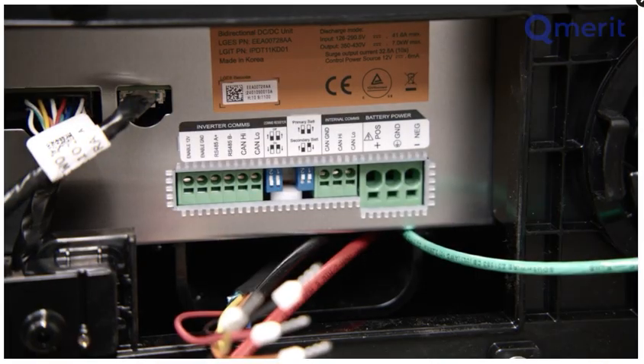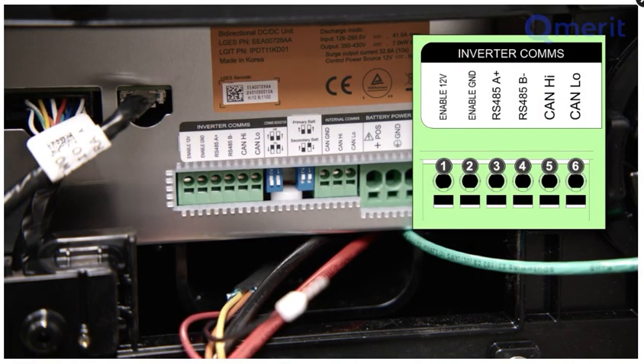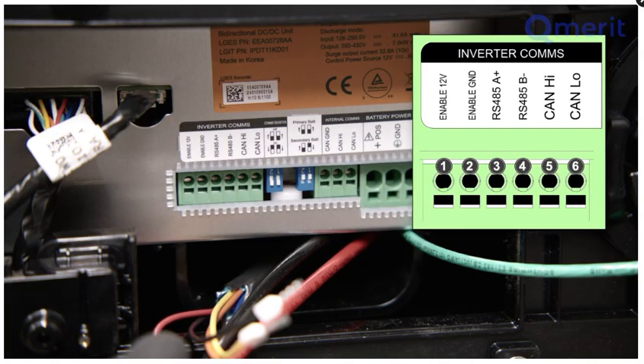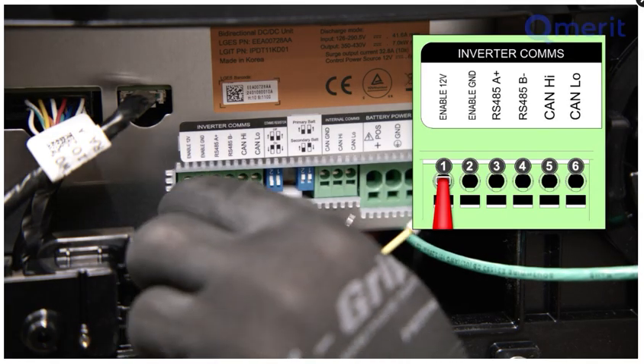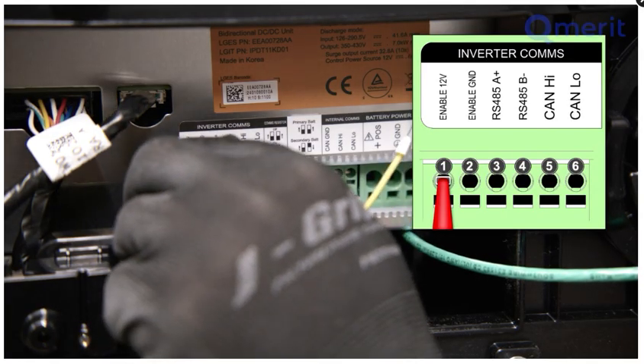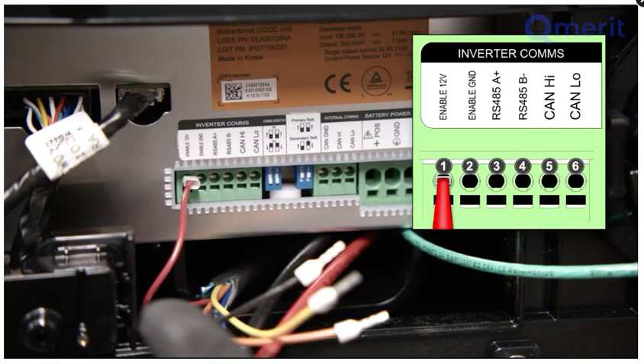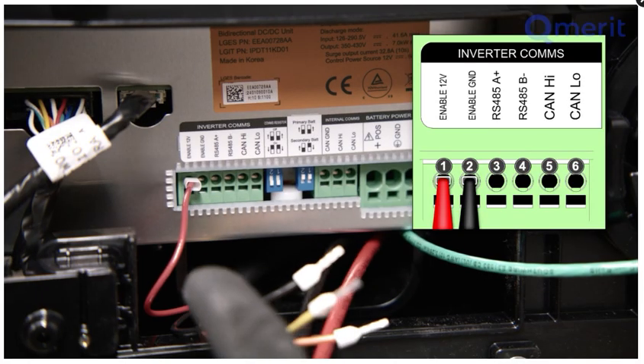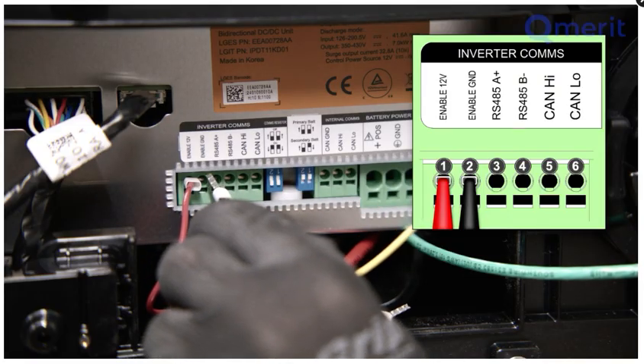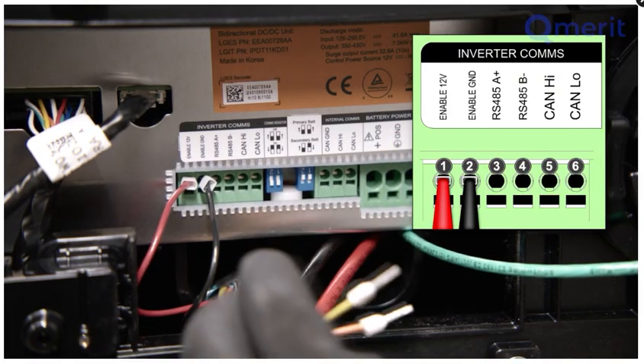Connecting the communication wires to the BCU. There are 4 communication wires. Connect the red wire to the Enable 12V positive line to terminal 1. These wires will click into place. If you need to remove a wire, press a flathead screwdriver in the slot below. Next, connect the black wire to the Enable ground wire to terminal 2.